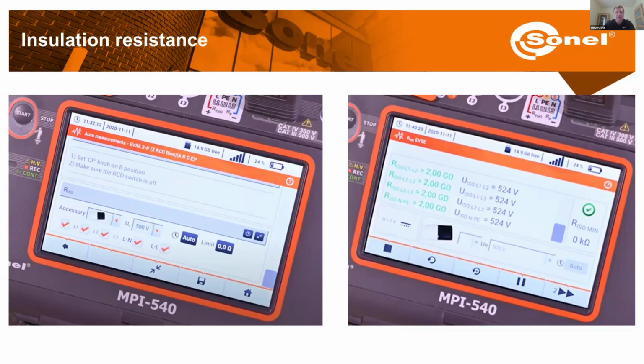And further, on the meters we can put the limits for our insulation resistance measurement. So here that would be 1 megaohm. And once the measured value is above this limit, the meter will automatically evaluate the results. So if everything is in green, that means it's good. Okay, so thanks to using this special algorithm, all the insulation resistance tests are just faster because the meter does all of the combinations itself. We don't need to connect, disconnect, and connect to another pair of conductors.